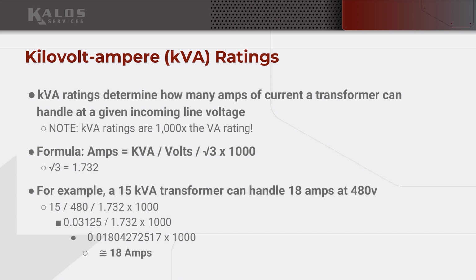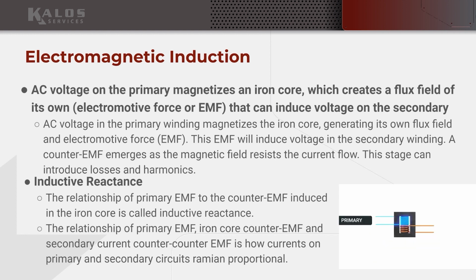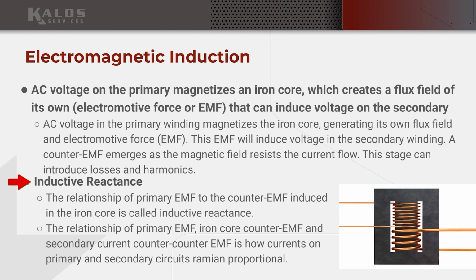But the kVA ratings that we see on our transformers are the limiting factor on how much we can load that transformer. And it's interesting that the relationship of your primary EMF versus the EMF produced in the core versus the counter EMF that's produced by the secondary is where, at least to a large degree, this kVA rating limitation comes into play. So as our secondary currents increase, those secondary currents create a counter EMF in the iron core, right? So if we go back to maybe this photo, as the secondary currents increase, there's a counter EMF being produced.